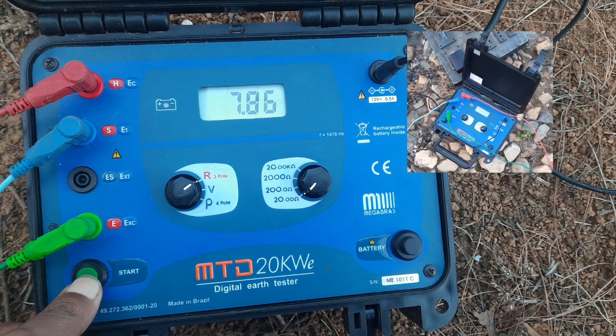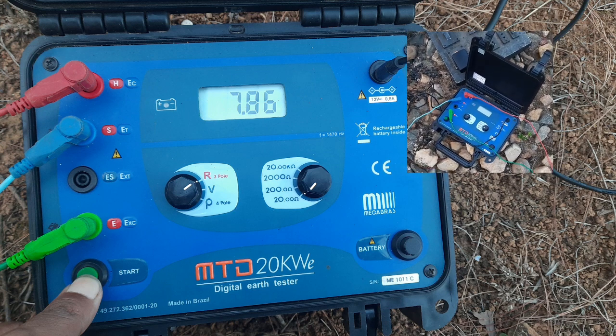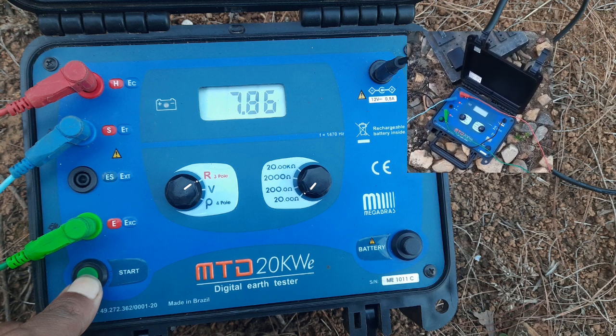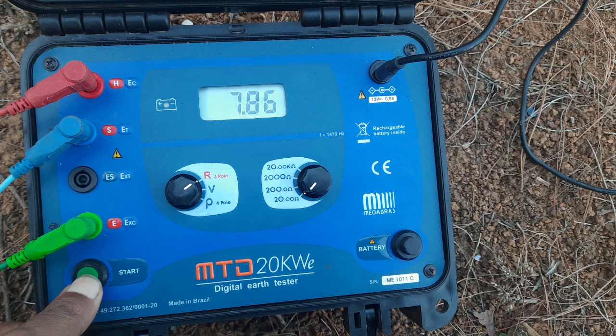When the selector switch is in the R position, E and ES will be internally shorted, whether or not the internal battery of this equipment has enough charge. You can check that by just pressing the battery test push button, and it will show you the status on the display.